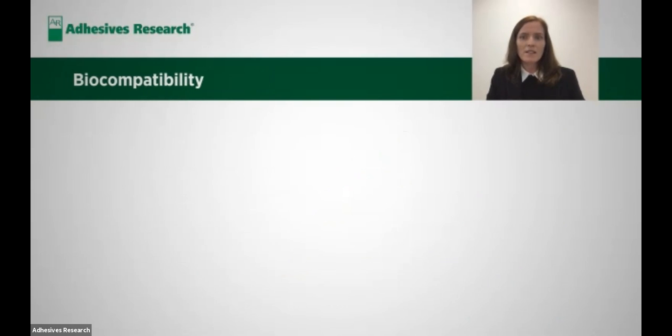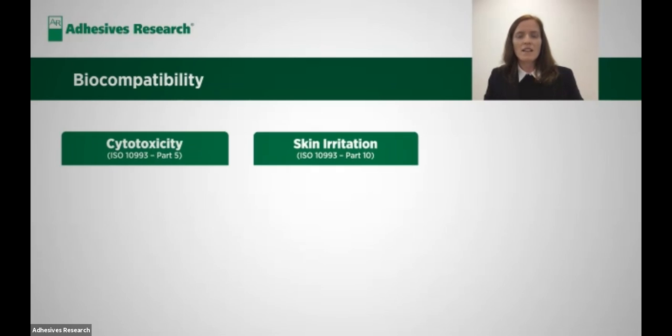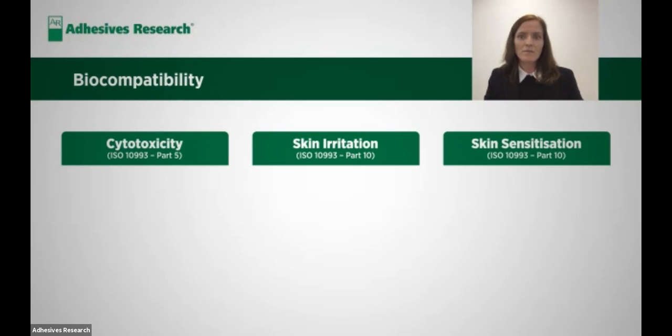Biocompatibility is testing a device to determine the potential toxicity resulting from bodily contact with a material or medical device. The testing needs to be completed according to ISO 10993 standards. The tests that are typically completed are cytotoxicity, skin irritation, and skin sensitization.